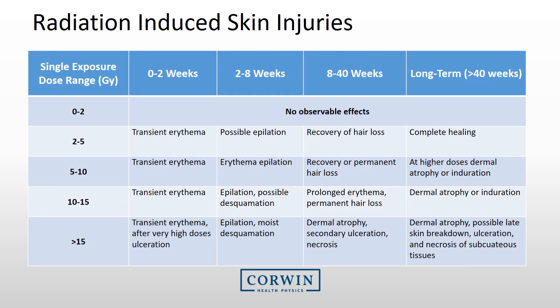It is good to have an idea of when skin injuries from radiation can occur. The threshold at which radiation-induced skin injuries can be observed is a skin dose of 2 gray. Below 2 gray, there are no observable deterministic effects. Above 2 gray, there is the possibility of skin burn, hair loss, and worse. A follow-up evaluation with the patient should be done for any procedures with a reported air kerma value greater than 5 gray.